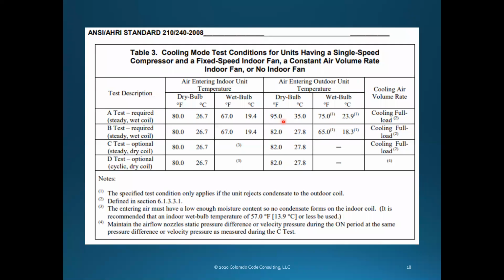At 95 degrees you might be lucky and designed to 95, but a lot of places aren't that lucky. So we always have to have the expanded performance data for every unit that shows what it actually does at these other temperatures—the information is out there. It's just that the software only has this information, this is all it's got, and it's wrong for our needs. It's right for the testing, but wrong for what we actually need to do.